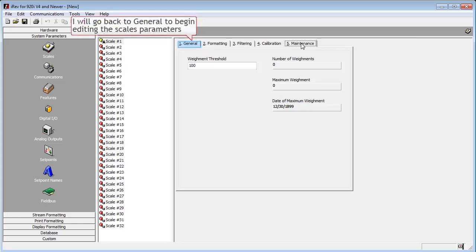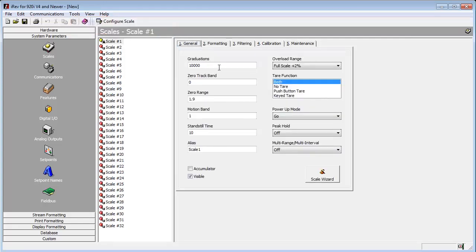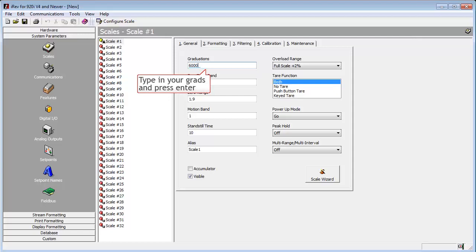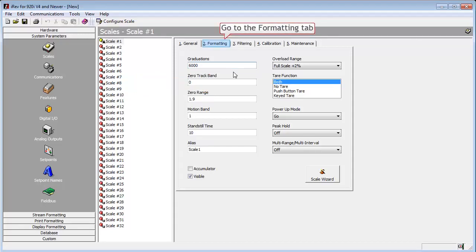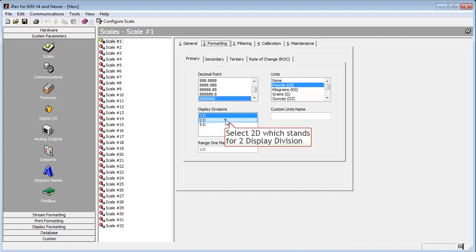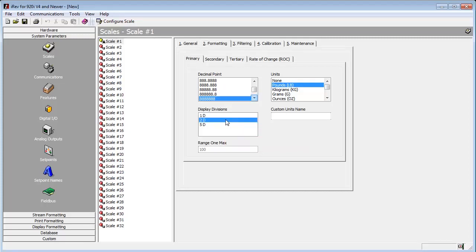First, we will set up our scale to be 120,000 pounds, counting by 20. We will change the grads to 6,000, then go to the Formatting tab to change the display divisions to 2D, and the decimal point to a fixed zero, while leaving the units at pounds.